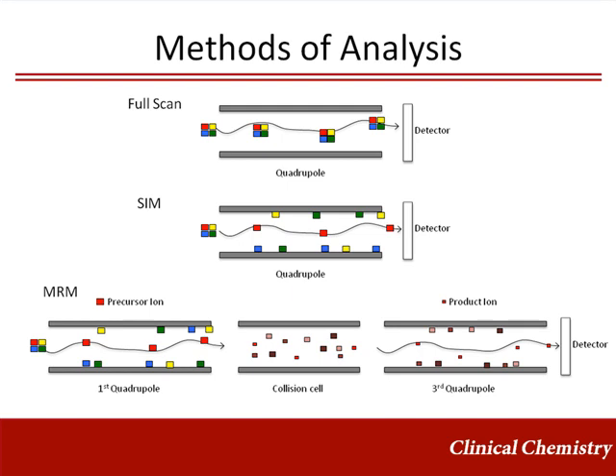Selected ion monitoring, referred to as SIM, can be used with known analytes of interest. For each analyte, an optimized voltage and frequency is determined. During analysis, the instrument continuously switches across each analyte-specific setting. This mode of analysis requires a single quadrupole, and no fragmentation occurs.